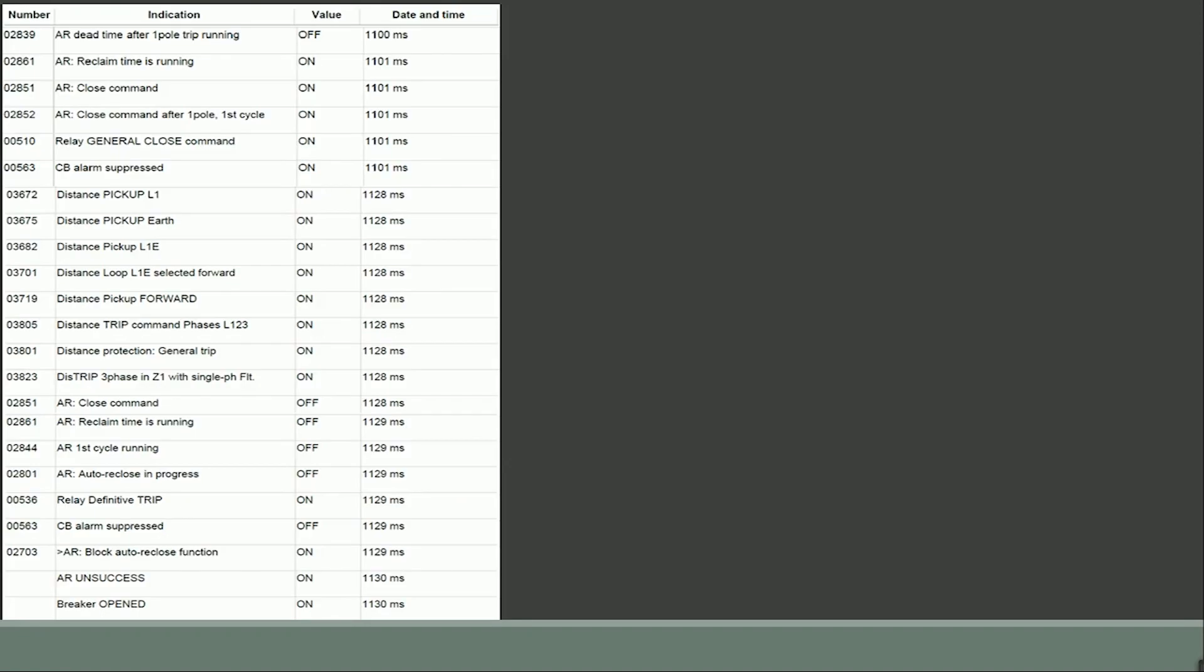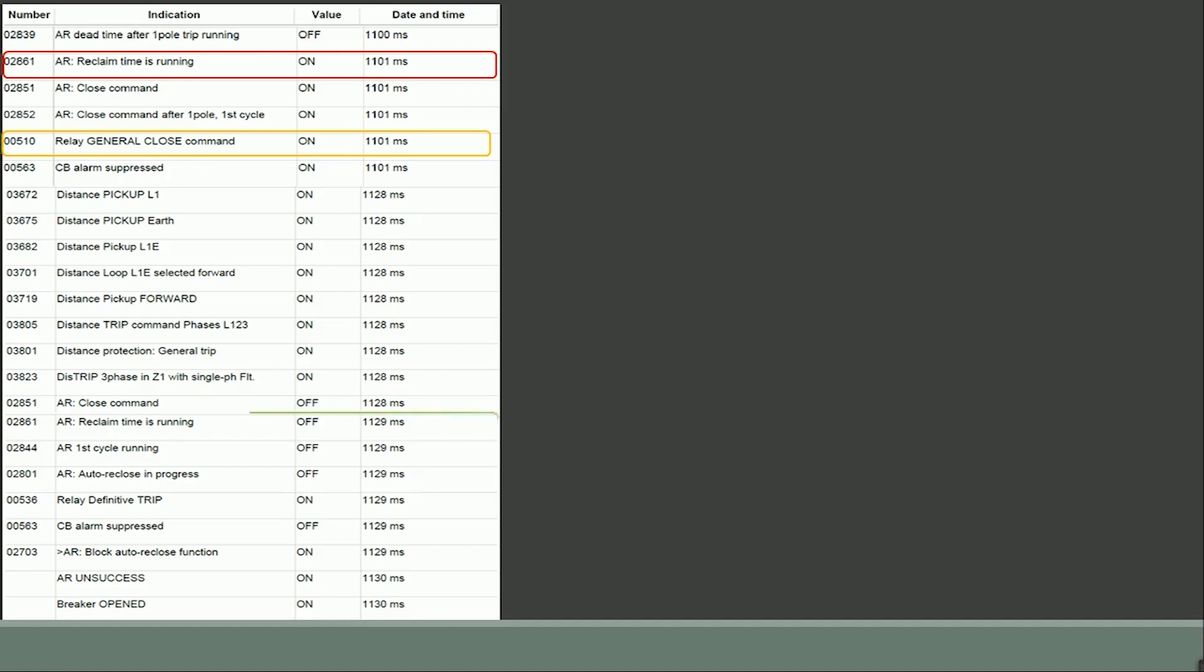The auto recloser reclaim time is started at 1101 milliseconds as per parameter number 02861. At the same instance relay issued close command at parameter number 00510. Reclaim time is turned off at 1129 milliseconds as highlighted.